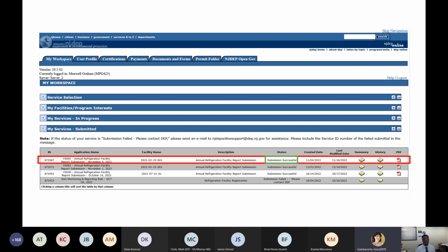Okay. There was also a few questions asking, does full charge mean per circuit or the sum of all charges of circuits? The way I understand it is that a circuit is what we're looking at. So it's going to be per circuit. That refrigeration loop, that one refrigeration loop, is considered a circuit. So if you've got multiple circuits, then that loop is independent of the other loop.